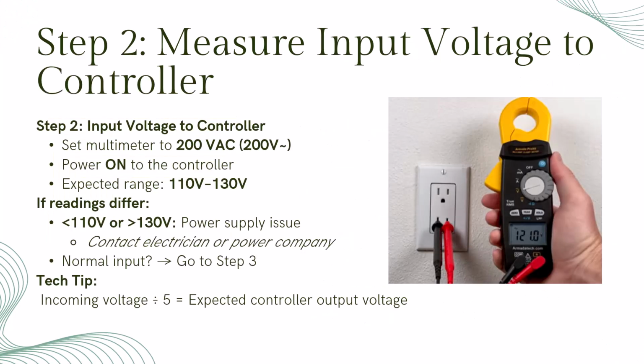Next, check the input voltage going into the controller. This is the highest voltage you'll find in the system, usually between 110 and 130 volts. Knowing this number helps you predict what the output voltage should be after the transformer. If the input voltage is outside that range, the problem isn't with your irrigation components, it's a power supply issue, and that's when it's time to call a licensed electrician or the utility company.